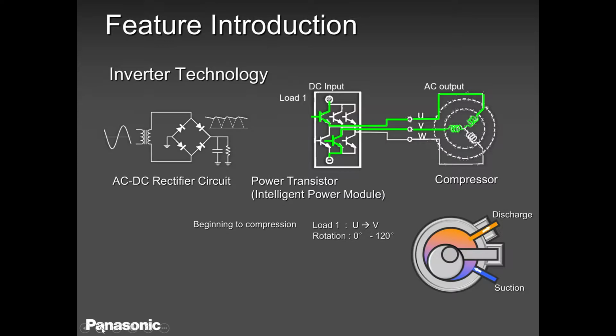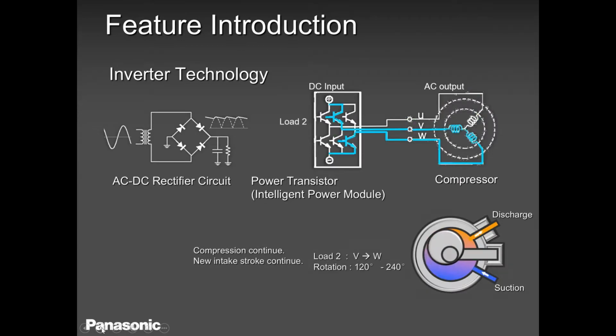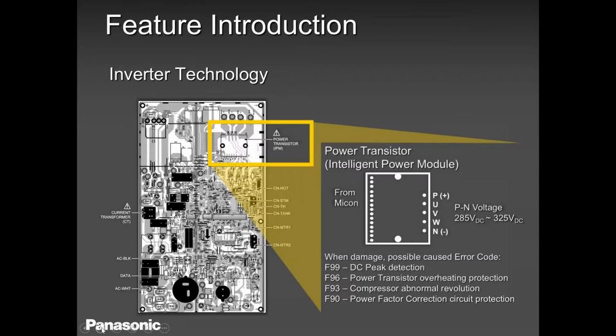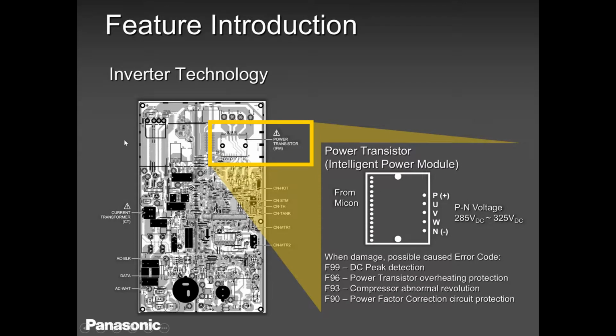So there you see the regulation of our three-phase compressor between U, V, VW, WU. Okay, 120 degrees to 240 and so forth. 240 to 360, you get a full stroke. So it's not too complicated, guys. It's a single board and a compressor. It's either the compressor or the board when you have a problem with F error codes, and these are the F error codes that I'm talking about: F99, F96, F93, and F90. We'll talk about this a little bit in detail as we progress. But bottom line, at the outdoor unit, this brain talks to the outdoor unit as well as to the indoor unit. And depending on what you are asking for, it corresponds with other components. If you want a defrost cycle, if you want to ramp down, if you want to ramp up, that's the brain of the unit.